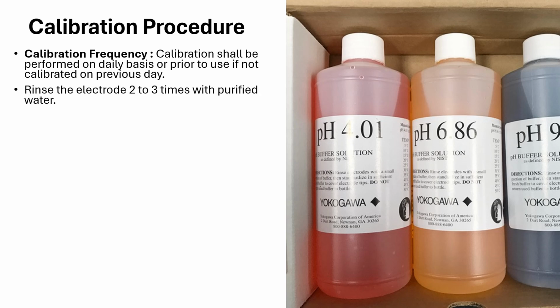First, rinse the electrode 2 to 3 times with purified water. This removes any residue from the previous measurement and prevents contamination, right? Next, after rinsing, gently wipe the electrode with tissue paper. Be careful not to press too hard, as the glass electrode is delicate and can be easily damaged.